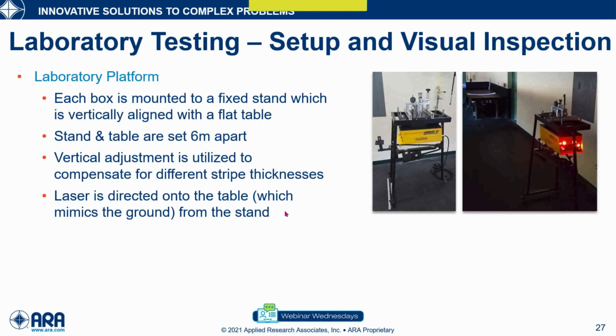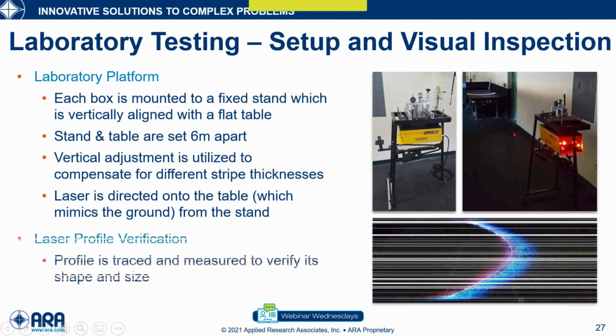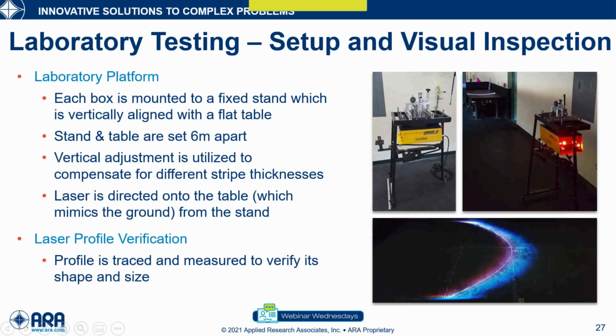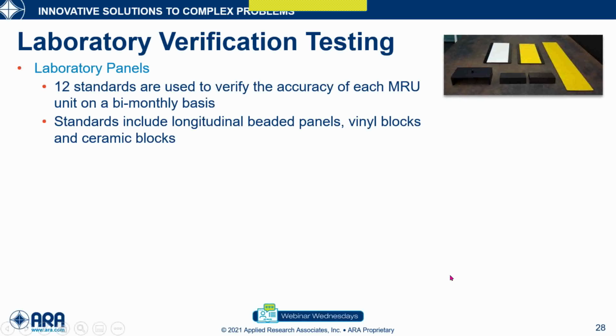So with the laboratory testing, the setup, and then the visual inspection and the calibration that I showed in the previous slides, we have this fixed stand, which is vertically aligned with this flat table right here. And as you can see, the distance between them is 6 feet, which is similar to when the unit is mounted on the truck, the distance the laser shoots. And we also have a vertical adjustment here to compensate for stripe thickness when we put it on the table. Usually we direct the laser onto the table, which pretty much mimics the ground. And the profile that is generated, which is a close shot right here, we measure it to verify its shape and then size. As you can see, the laser profile should be parabolic, and this is almost close to 39 inches.